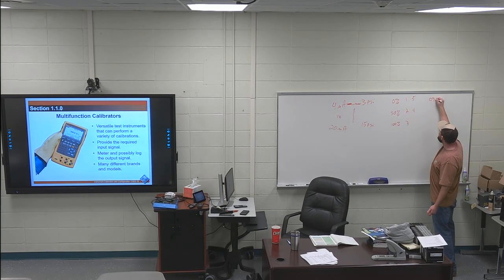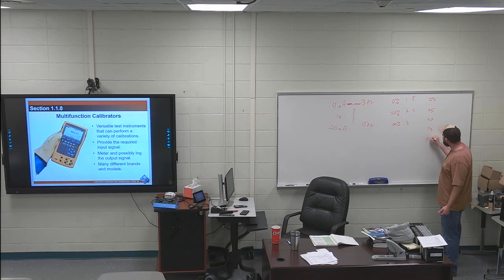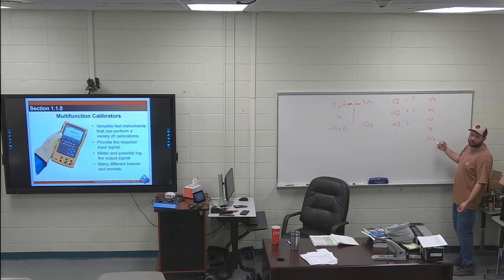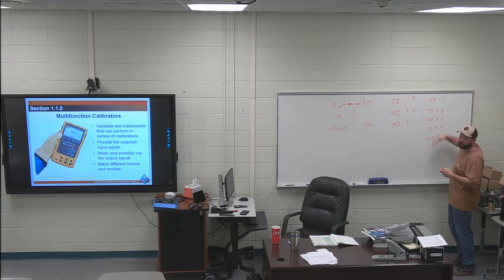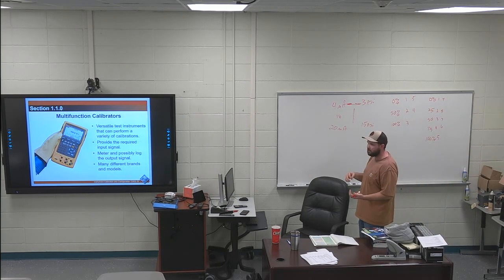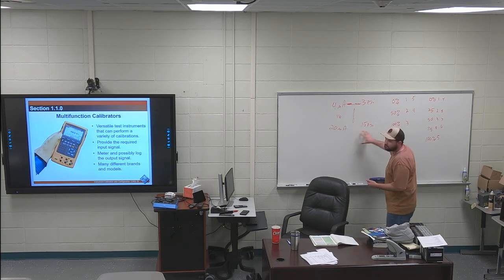So 0 to 100% in steps: 0, 25, 50, 75, 100%. Same thing. I'm going 1, 2, 3, 4, 5, 6, 7, 8, 9. You're not just doing 5 different ones, you're doing 9, but at 5 different points. Does that make sense? You're going all the way up and then back down. So that's your zero and span, your 3-point calibration, and 5-point, in order of least accurate to most accurate.